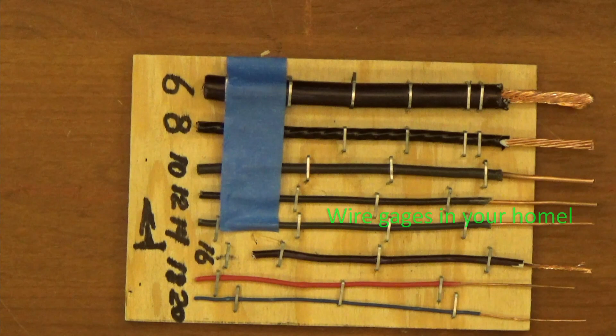Now the thing about gauges - and I'm not going to explain why - the smaller the number, the thicker the wire. The insulation doesn't matter, it just needs to be adequate. These numbers correlate to the actual conductor, not the size of the insulation. So notice that 6 is the thickest and 20 is the thinnest. The only wires you would use for power in a building are 14 gauge or larger - larger in size, smaller in gauge.